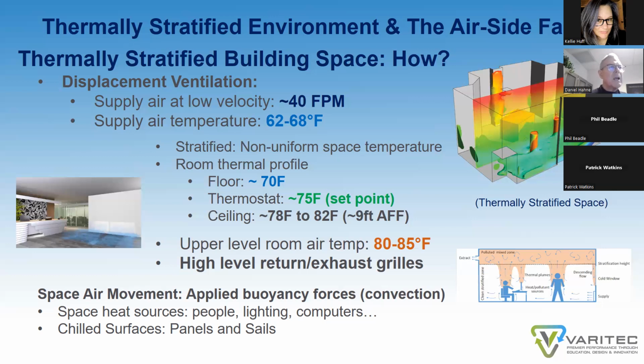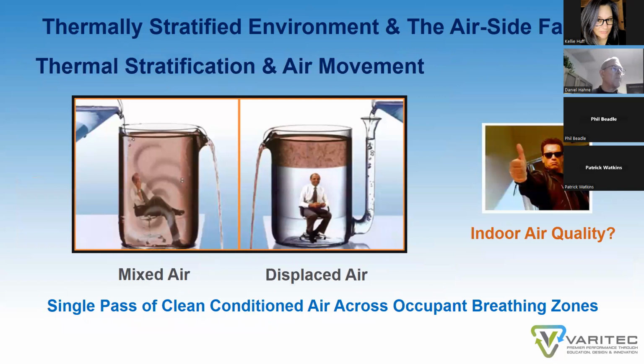So what drives air in the space if it's not fan energy injecting air at high velocity? Heat. Heat sources in the space are the source for moving air. Consequently, where you have an occupant of 98 degrees and the space set point is 75, that warm occupant has a vertically rising thermal plume of roughly 30 feet per minute that is carrying clean, conditioned air across the breathing zone as warm, contaminated air is transferred to the upper levels of the room, where it is exhausted not only from the space, but from the building.